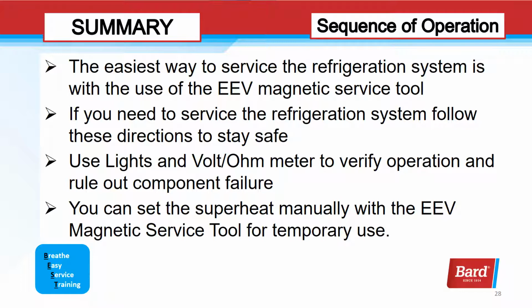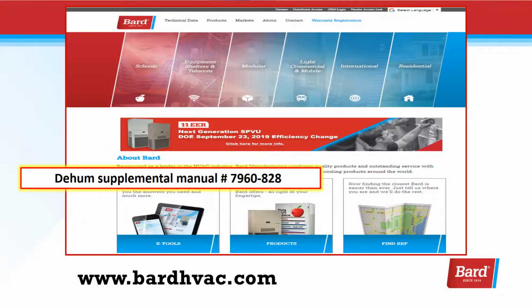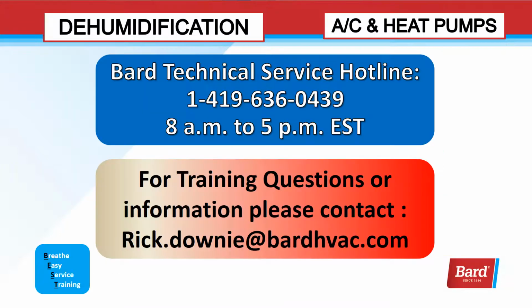Here we learned how to use the lights and a volt ohm meter to verify operation and rule out component failure, and that we can set the superheat manually with the EEV magnetic service tool for temporary use. Remember that the DHUM supplemental manual, if you would like these instructions in writing, manual 7960-828 is available from bardhvac.com.